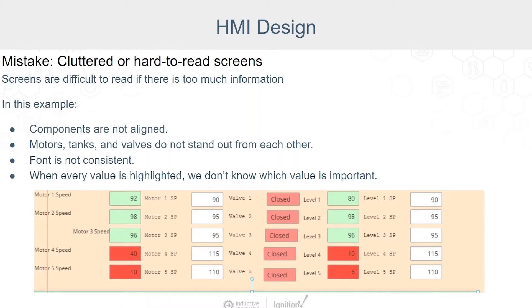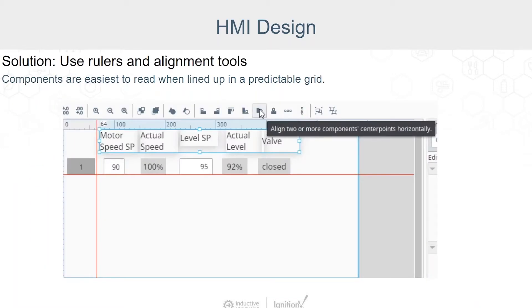Let's have a look at a cluttered and hard-to-read screen. Screens are difficult to read if there's too much information, so you should consider grouping your data into tabs or grids. In this example, the components are not aligned, the motors and tanks and valves do not stand out from each other, the font is not consistent, and we don't know which highlighted component is important because almost everything is highlighted. One trick that goes a long way is to use grids and rulers — making sure things are lined up correctly and appropriately sized will greatly improve legibility.